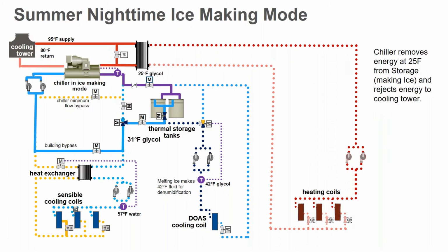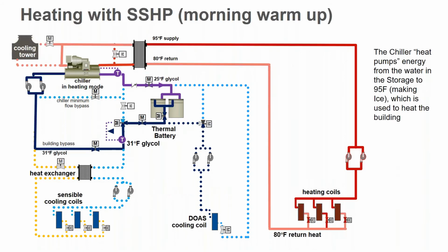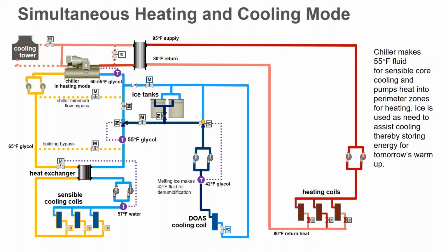Summer, nighttime ice making. Since we started on the cooling side of things, it's the same as it was before. We're charging the tanks, or rather, we're actually discharging the energy from the tanks. We're taking the energy out and rejecting it out on the cooling tower. Morning heating with the DOAS system, it's the same. You're putting heat wherever you need it in the heating coils, and you are making ice. On the simultaneous nature with the DOAS, as I said, you can be running the chiller. The ice tanks can absorb energy from both directions, or it can be helping cool, depending on if it's overloaded.